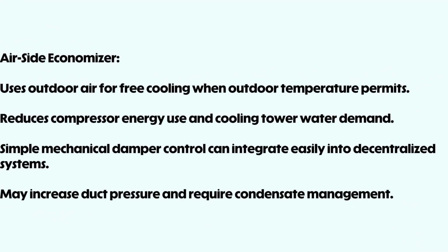To improve efficiency, many decentralized units include economizers, systems that use outdoor conditions to reduce compressor energy use. An airside economizer introduces outdoor air directly into the HVAC unit when outdoor conditions are cool enough. This provides free cooling, reducing compressor runtime, and extending equipment life. Advantages include lower energy consumption, reduced tower water usage, and improved indoor air quality through increased ventilation. However, they require careful control of humidity, proper drainage for condensate, and may increase system pressure drop.